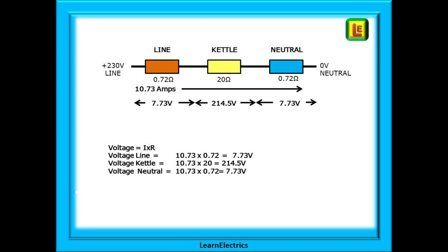Calculating individual voltage drops: 10.73 amps times 0.72 ohms gives 7.73 volts drop for each of the line and neutral cables. This means only 214.5 volts is available for the kettle. The total voltage lost in line and neutral is 15.5 volts — well above the permitted limit for non-lighting circuits of 11.5 volts. We're already in trouble.